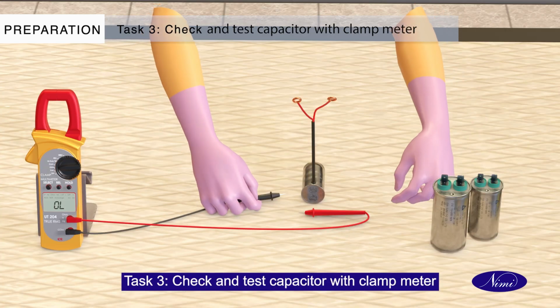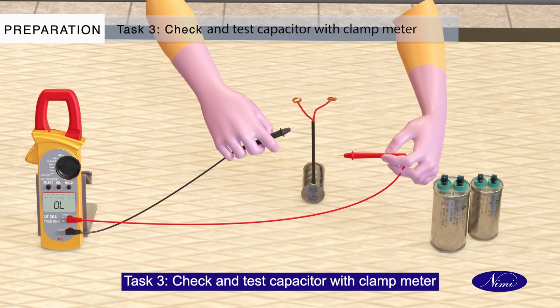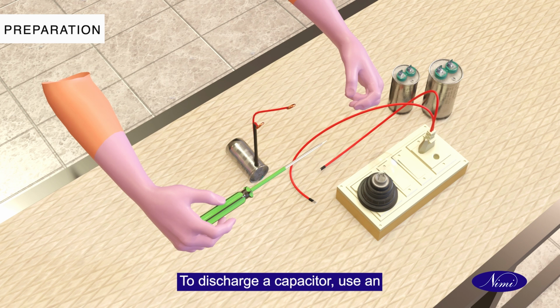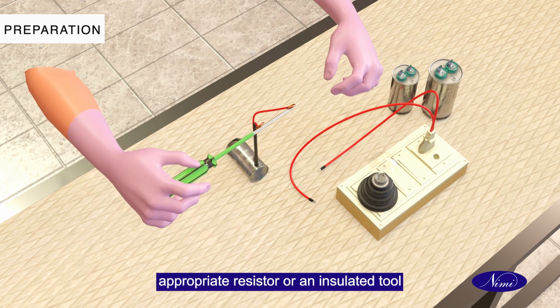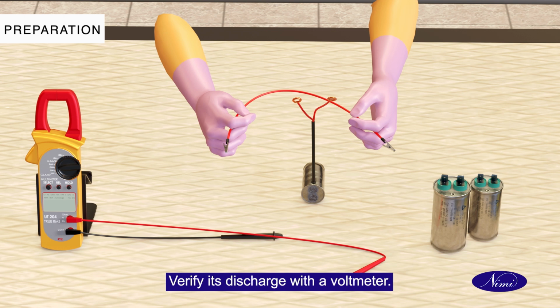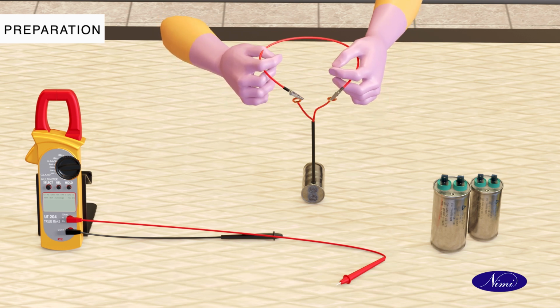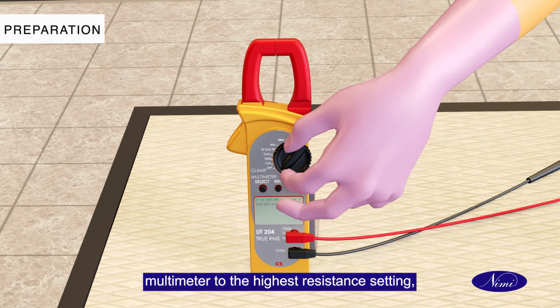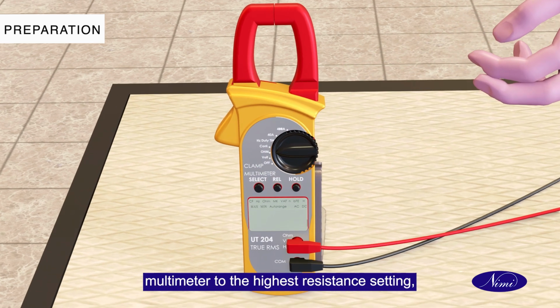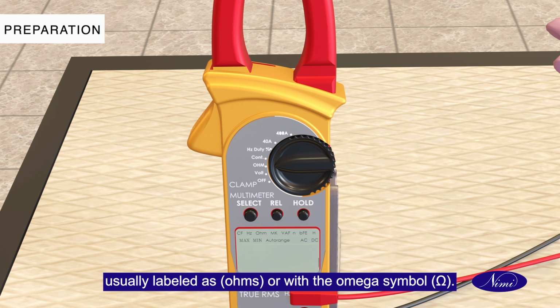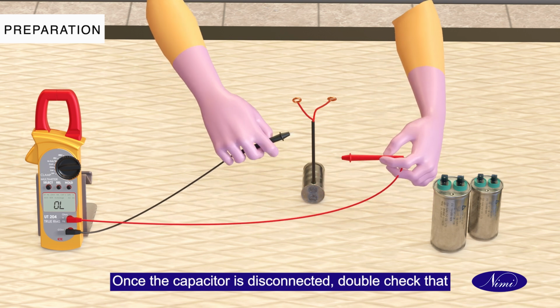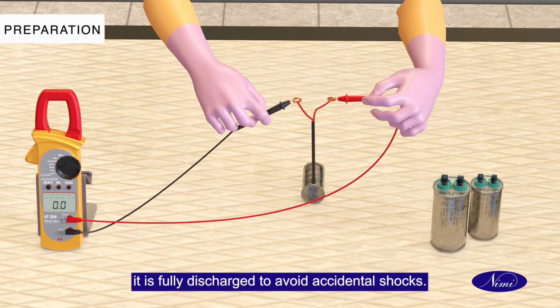Task 3. Check and test capacitor with clamp meter. To discharge a capacitor, use an appropriate resistor or an insulated tool to bridge across its terminals. Avoid using bare hands. Verify its discharge with the voltmeter. Turn off the power source and set your multimeter to the highest resistance setting, usually labeled as ohms or with the omega symbol. Once the capacitor is disconnected, double check that it is fully discharged to avoid accidental shocks.